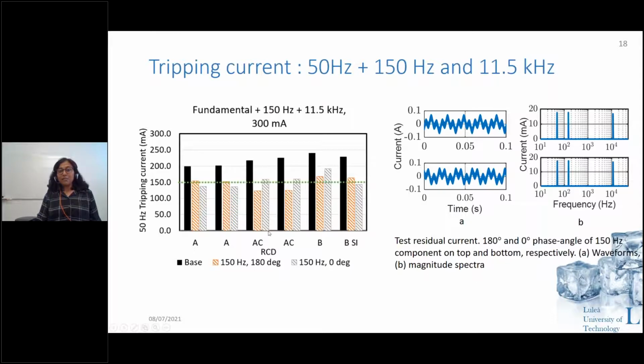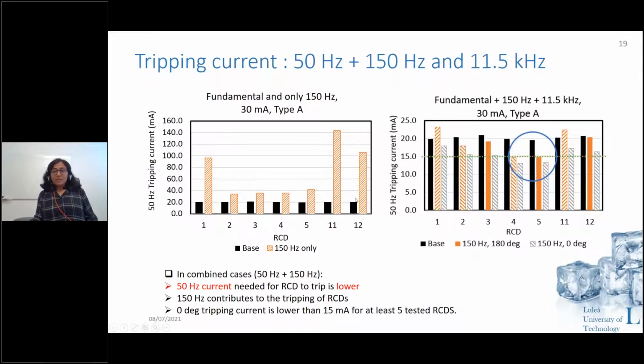And similarly for type AC RCDs, here you have for 150 hertz and 180 degrees, even below 150 milliampere. So this is also a false trip condition. And also overall, if we saw that for RCDs with 150 hertz and 0 degrees, they tripped with a lower fundamental current as compared to the base case.